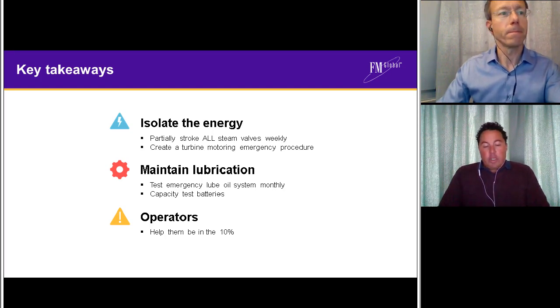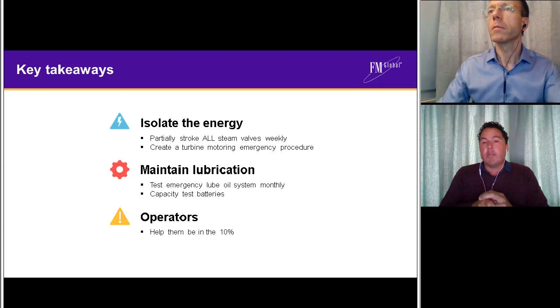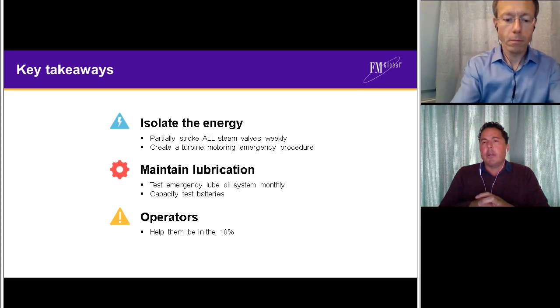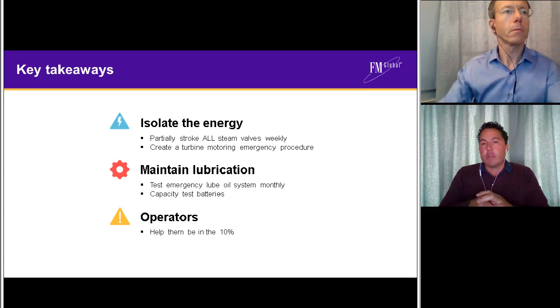Thanks, Michael, for the question. I guess in short, my answer is I'm not aware of any additives that can be introduced to the oil to meaningfully reduce the fire risk. There may be some in development, but as far as I know, the only thing that I've come across so far that meaningfully changes the fire risk on a steam turbine is using fire resistant lubricant such as phosphate ester type products that are commonly used in aero combustion turbines and aero derivative combustion turbines.